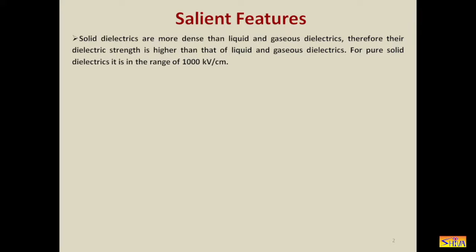So in solid dielectrics, the molecules are more dense, therefore their dielectric strength is the highest. For pure solid dielectrics, it is in the range of 1000 kV per centimeter. For liquid, I had told you this is 100 kV per centimeter. For air, it is 30 kV per centimeter. So you can see the difference. For pure solid dielectrics, it is 1000 kV per centimeter.